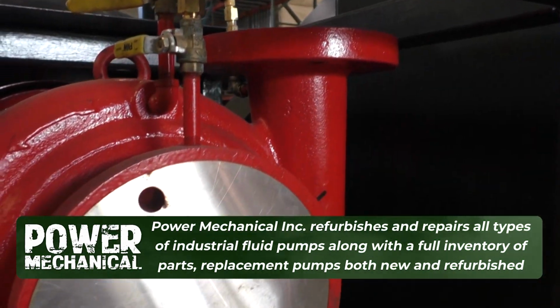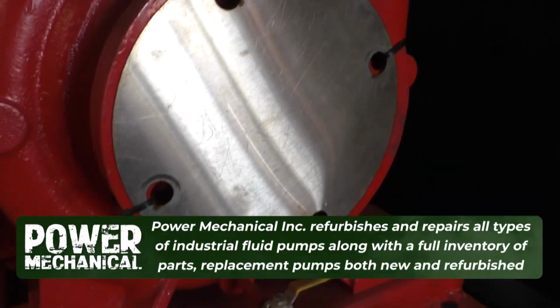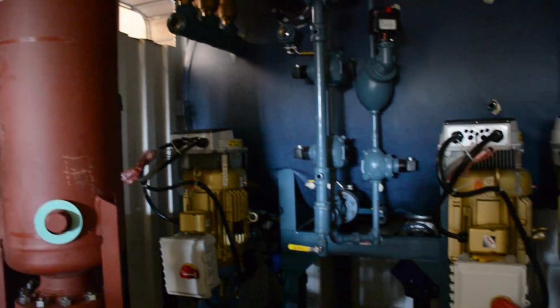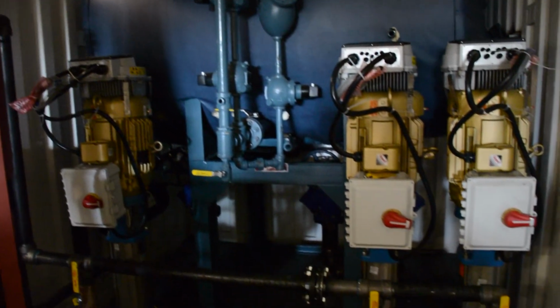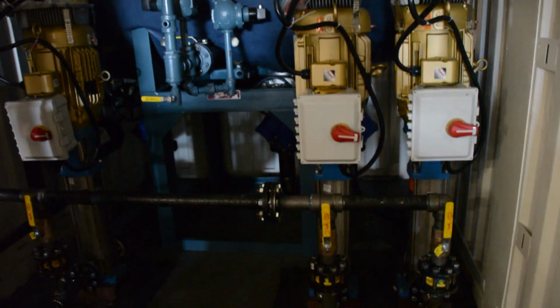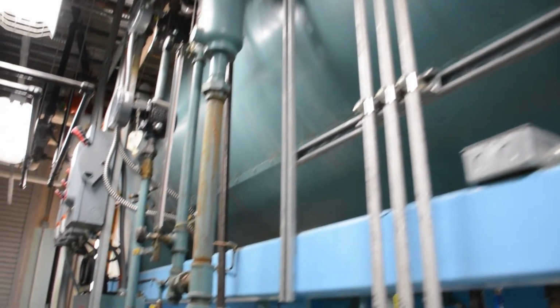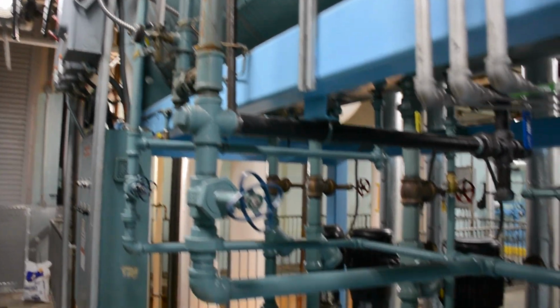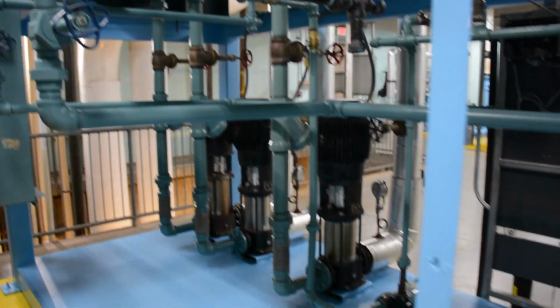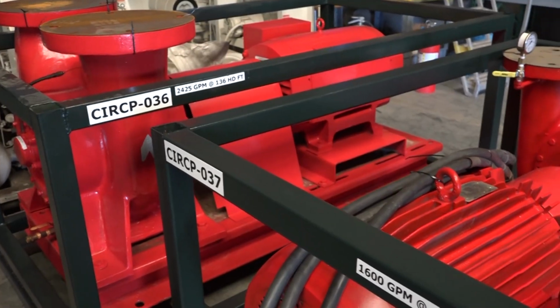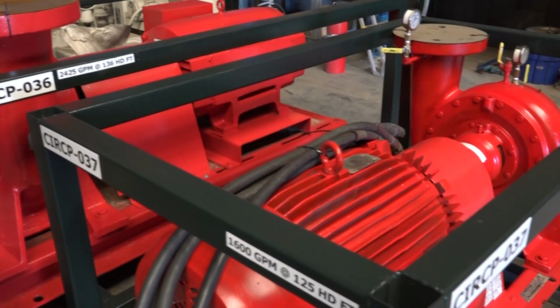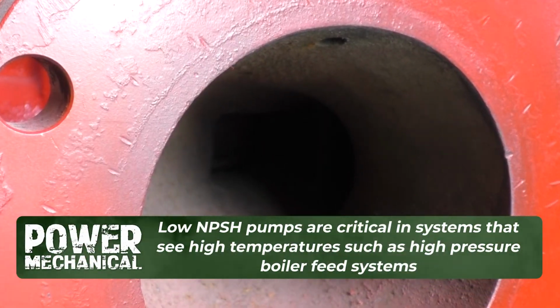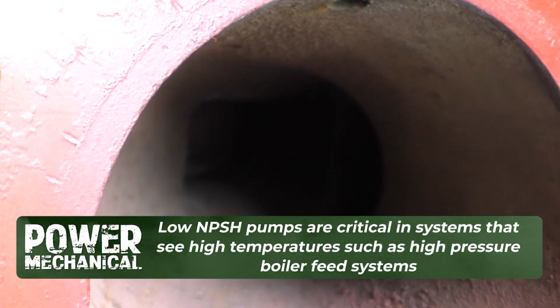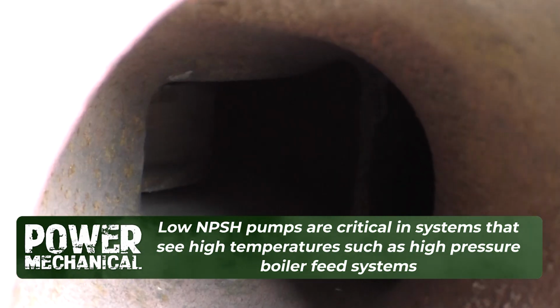Some boiler feed applications may see where it is necessary to utilize what's called a low NPSH pump. These specially designed multi-stage centrifugal pumps are engineered with an oversized first stage impeller and chamber that is essentially better suited for handling this high temperature feed water for many boiler applications. The design makes it better suited for the higher stresses that some systems may see due to poor suction pressure and near boiling liquid temperature.